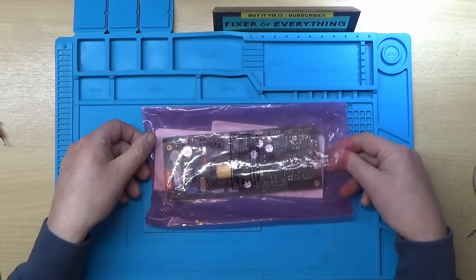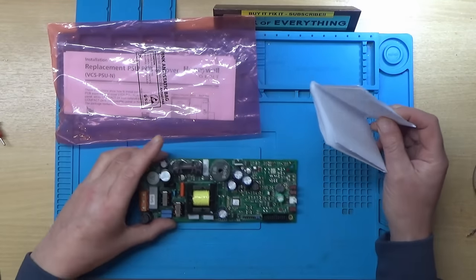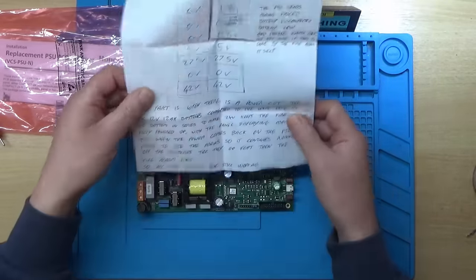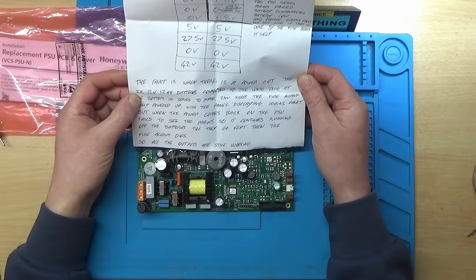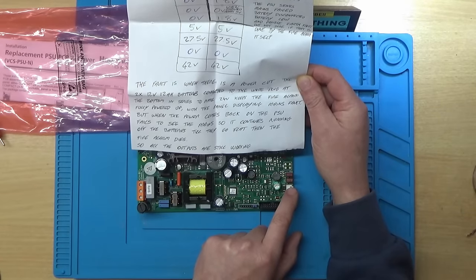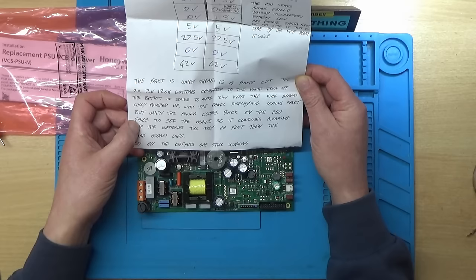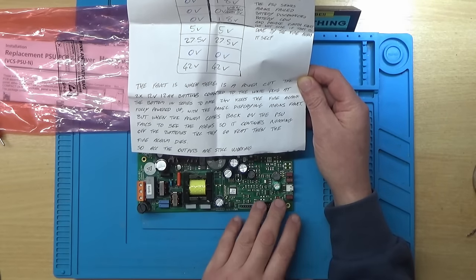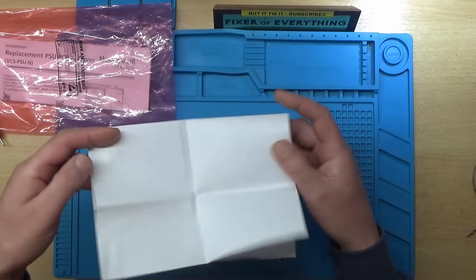A viewer called Mark sent in a power supply for a fire alarm with a note describing the fault. When there's a power cut, two 12-volt 12-amp-hour batteries connected in series to make 24 volts keep the alarm fully powered, with the panel displaying a mains fault. But when the power comes back on, the power supply fails to detect the mains and continues running off the batteries until they go flat and the fire alarm dies. All outputs appear to be working.